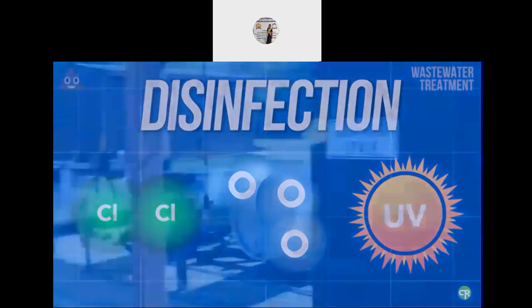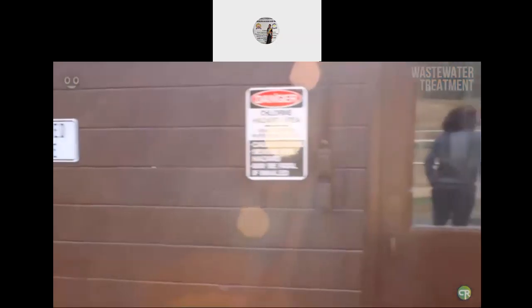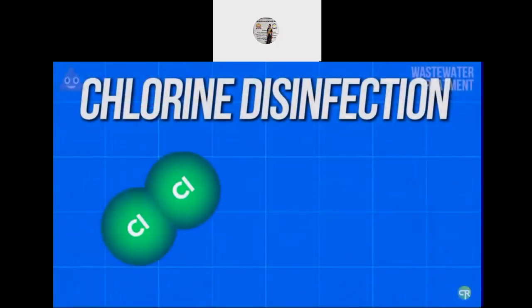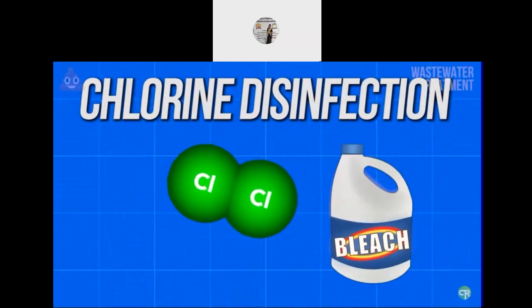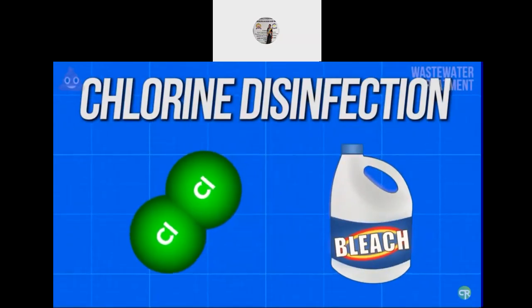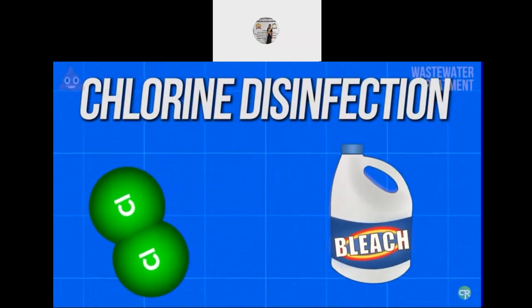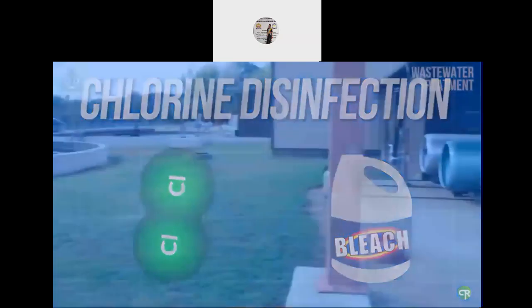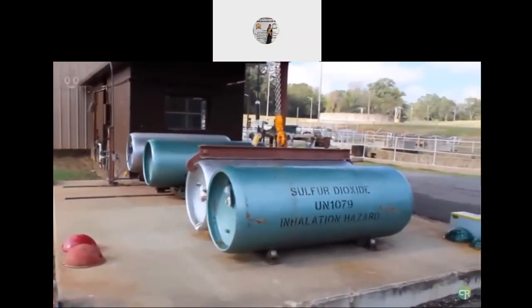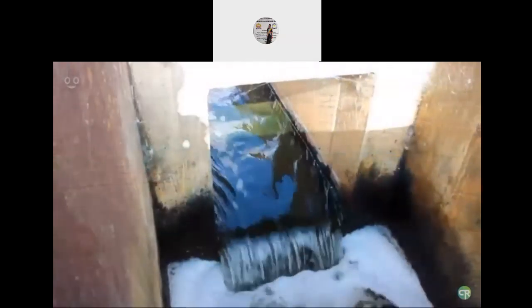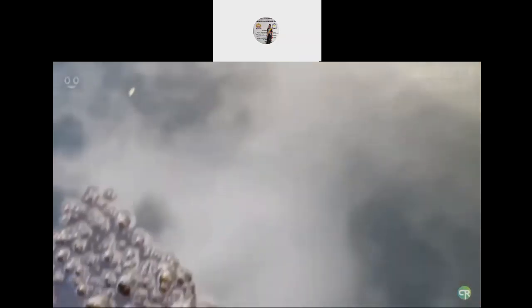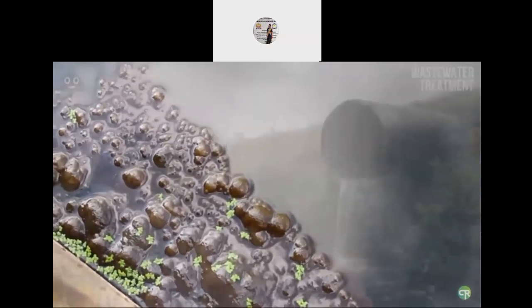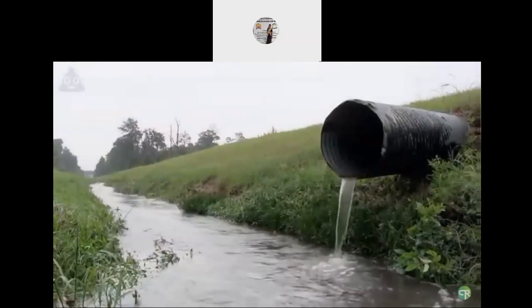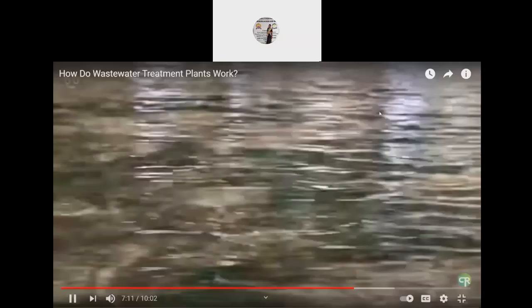Chlorine disinfects the water through chemical disinfection. Chlorine, which you can think of as concentrated bleach, is added to the effluent here to kill off any remaining bacteria and organisms still living in the water. When chlorine is added to kill off the bacteria, it then has to be removed before it can be discharged, as to not kill off anything in the discharge location. After this, the water is safe enough to discharge into a stream or lake.